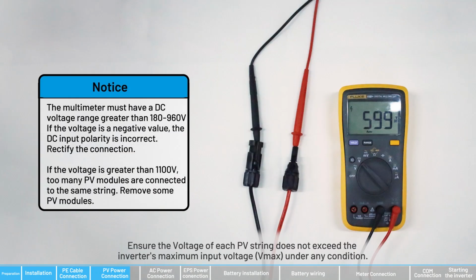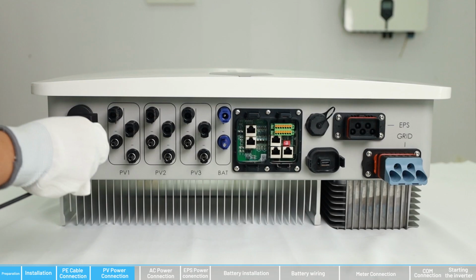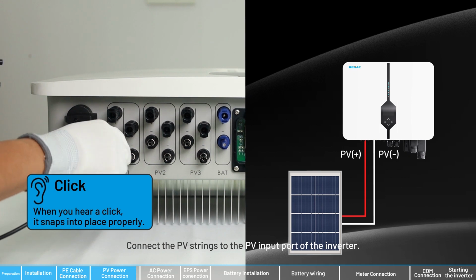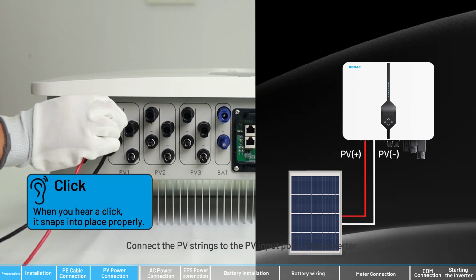Ensure the voltage of each PV string does not exceed the inverter's maximum input voltage, Vmax, under any condition. Connect the PV strings to the PV input port of the inverter.